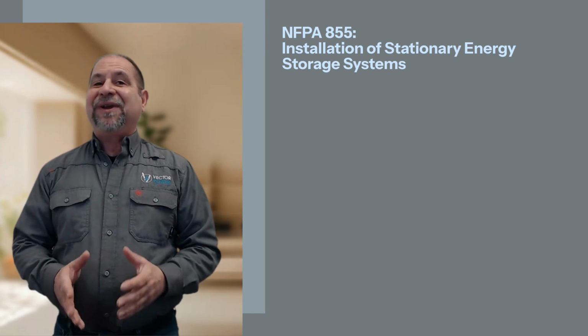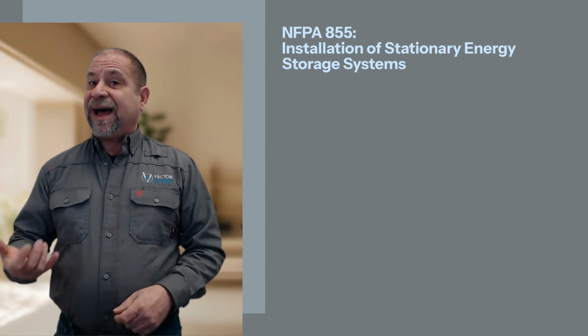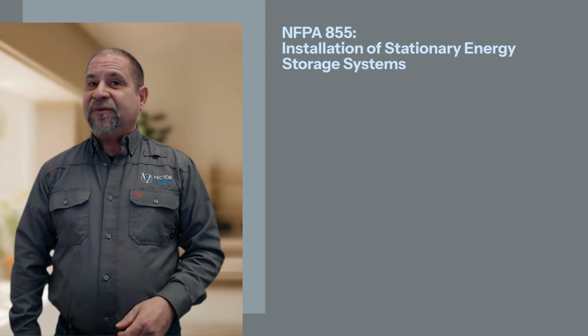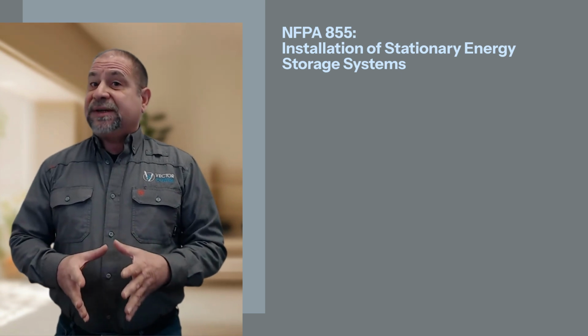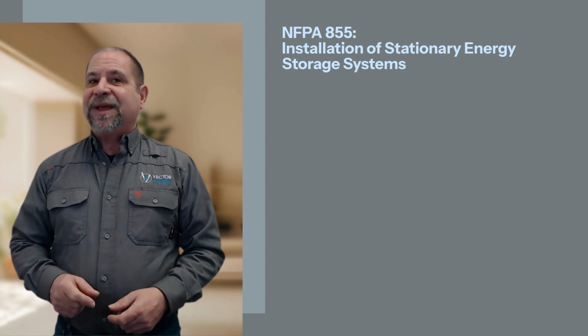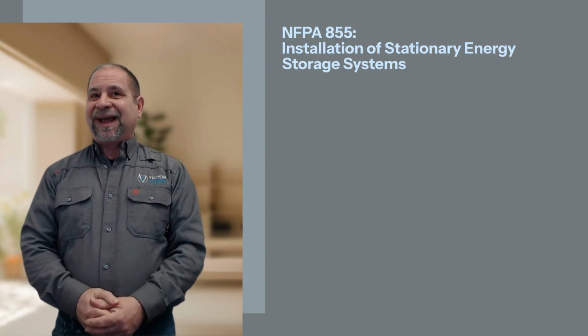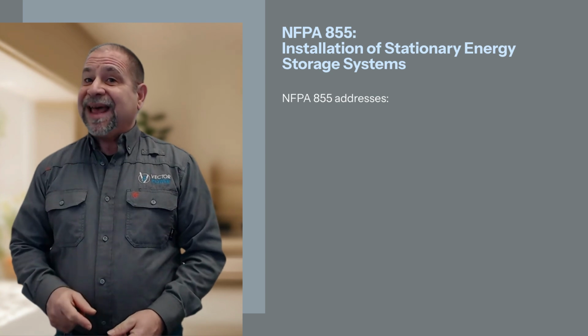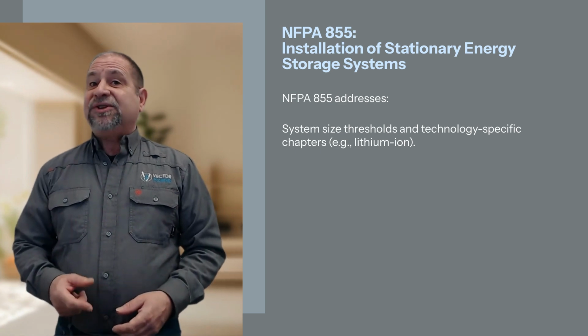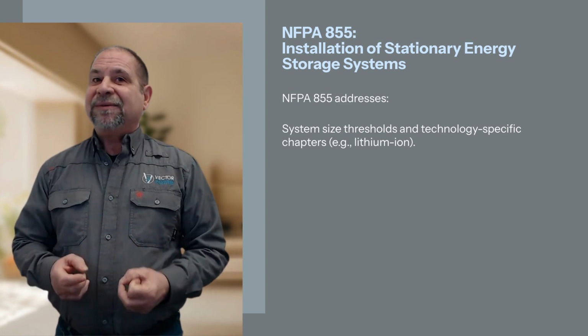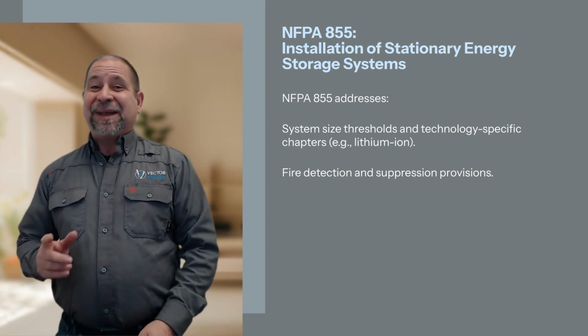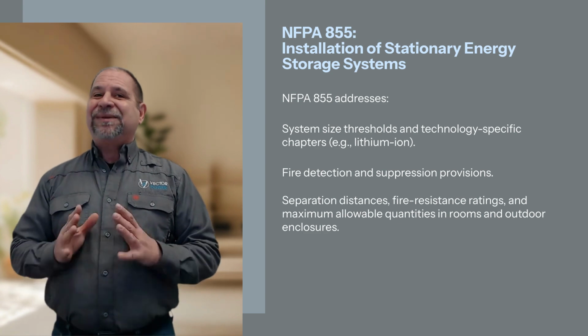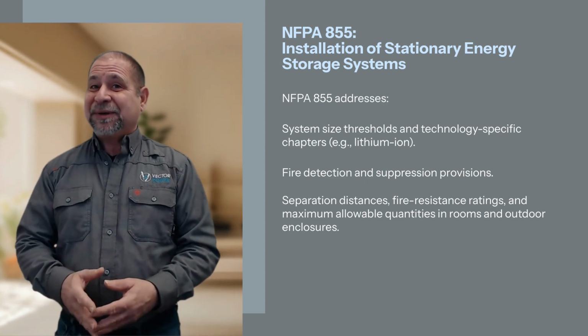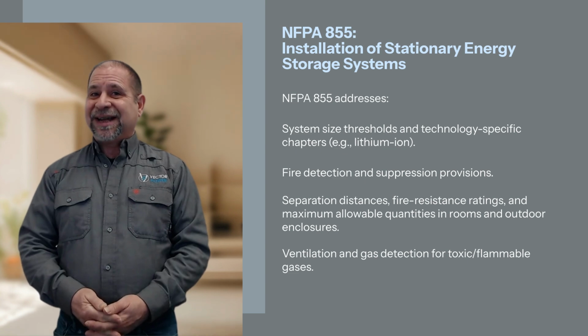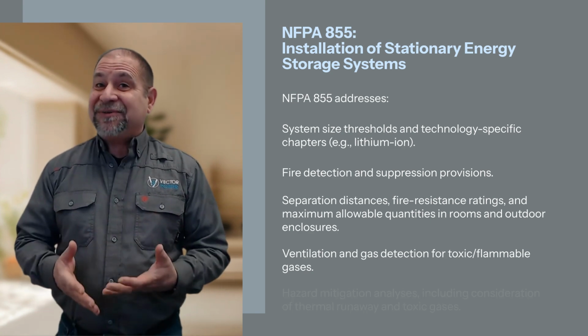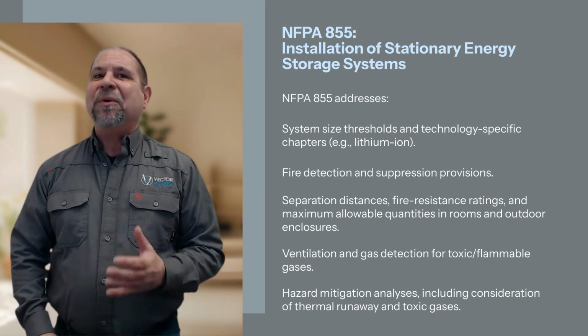NFPA 855, installation of stationary energy storage systems. NFPA 855 provides minimum requirements for mitigating hazards associated with stationary energy storage systems, including battery systems, and is referenced by NFPA 1 Fire Code and the International Fire Code. NFPA 855 addresses system size thresholds and technology specific chapters, for example, lithium ion; fire detection and suppression provisions; separation distances, fire resistance ratings, and maximum allowable quantities in rooms and outdoor enclosures; ventilation and gas detection for toxic and flammable gases; and hazard mitigation analyses, including consideration of thermal runaway and toxic gases.